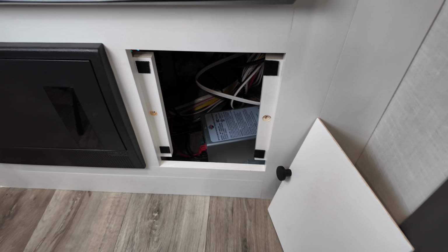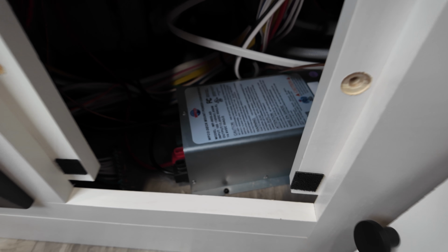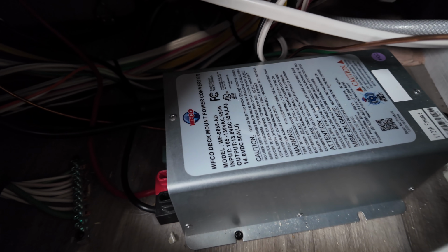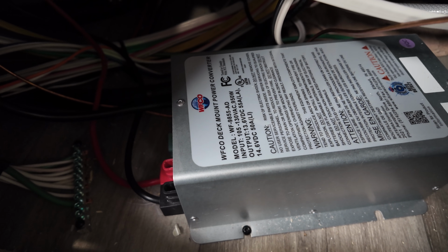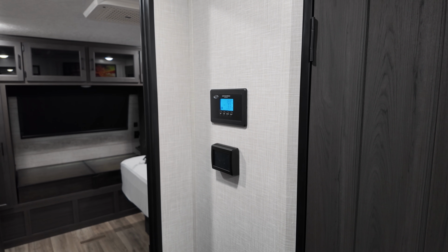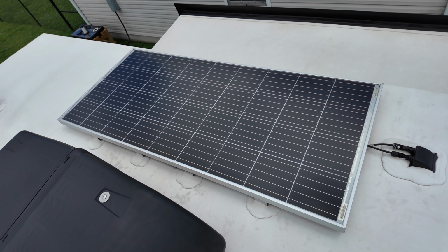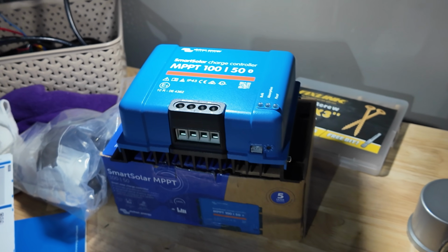Where wiring comes into question is if you're replacing the OEM converter with something capable of supplying power that exceeds the rating of the existing wiring. For the solar charge controller, it's when I add more panels that can exceed 30 amps and swap to a higher amperage charge controller that I need to take a look at that wiring.